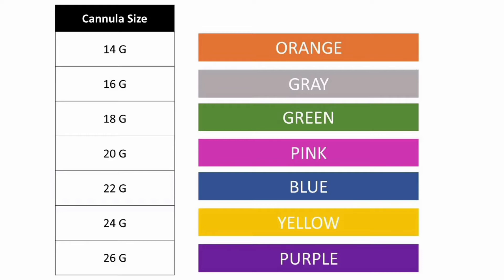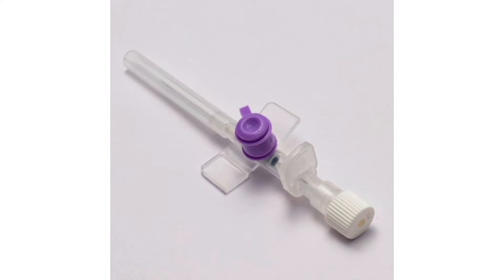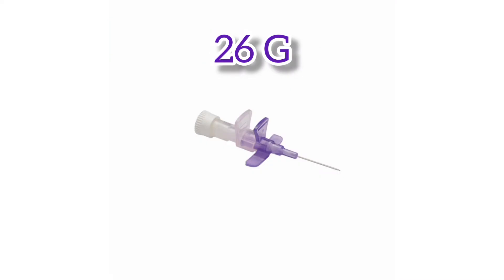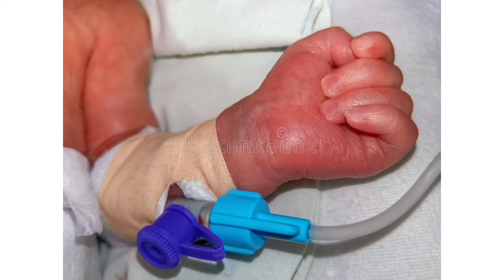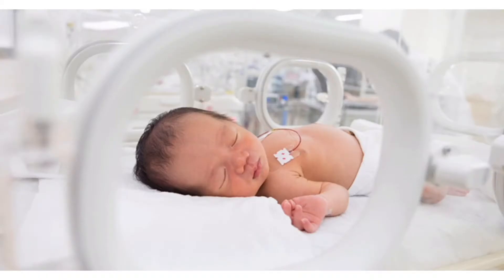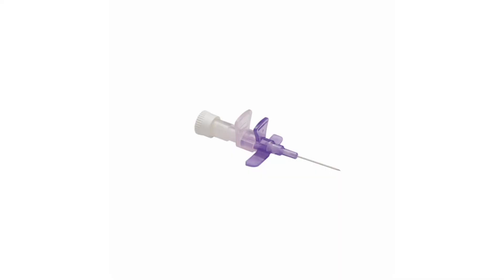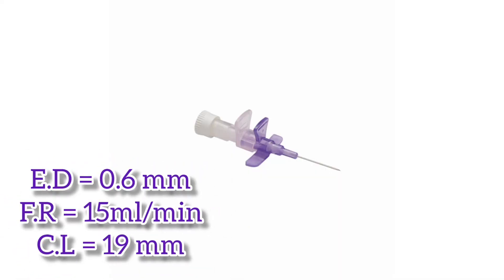We will start from the purple colored cannula having gauge 26, which is the highest number. You can predict that with higher gauge there is less external diameter and flow rate, making it best used in neonates and infants who require less flow rate. Its external diameter is 0.6 mm with a flow rate of 15 ml per minute.